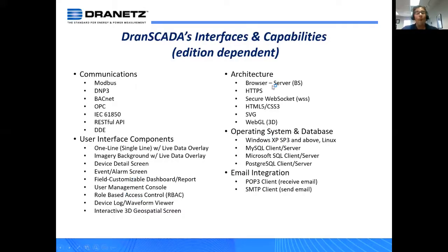Well, the architecture, it is web browser-based software. It has a built-in web server, regardless of the standard all the way up through the professional edition. Very secure, HTTPS. It's developed in HTML5, so it's very, very mobile device capable with a responsive web server. Operating systems, anything from XP and above, and also Linux. If you run in a Linux environment, it is compatible with that. Various SQL and Microsoft SQL servers, as well as email integration to push out emails and receive emails from various systems. So pushing out an email may be an alarm notification that it sends to a distribution list, as an example.